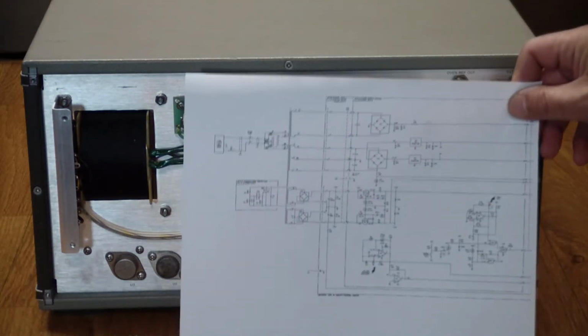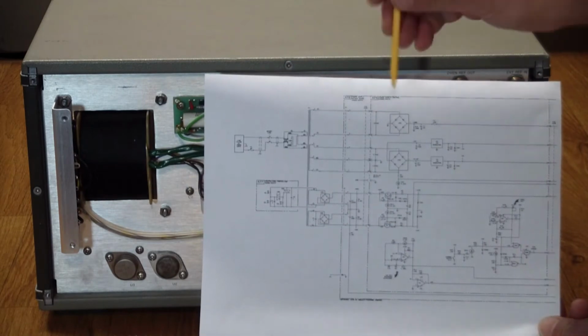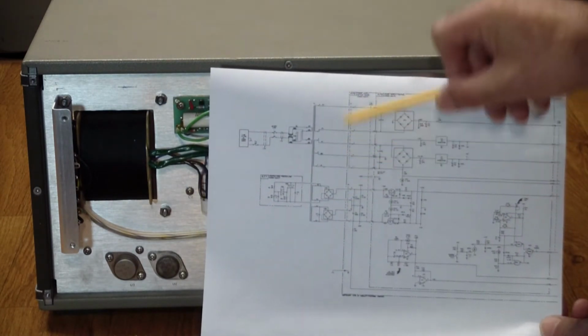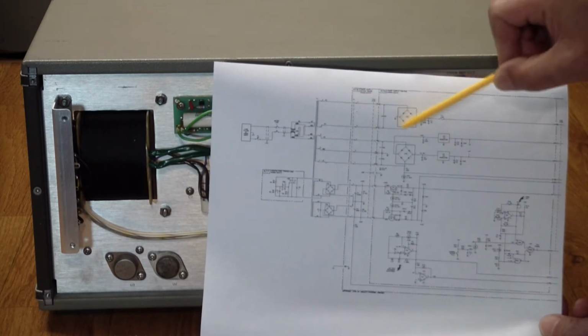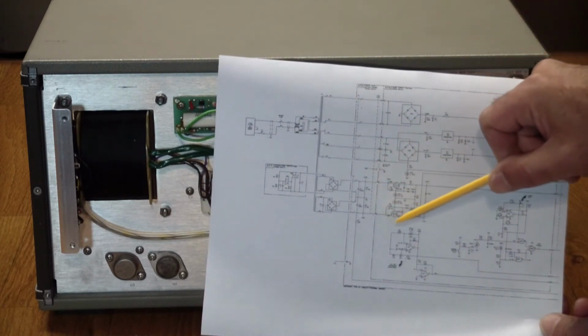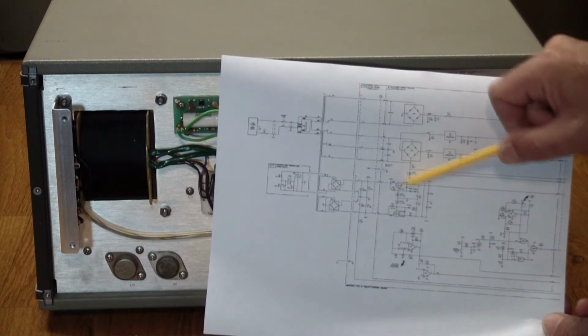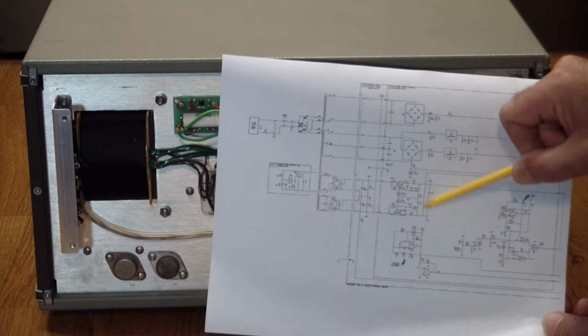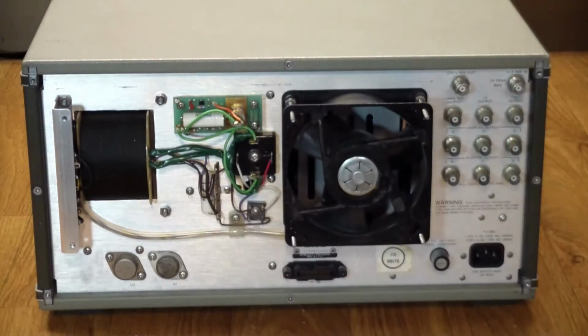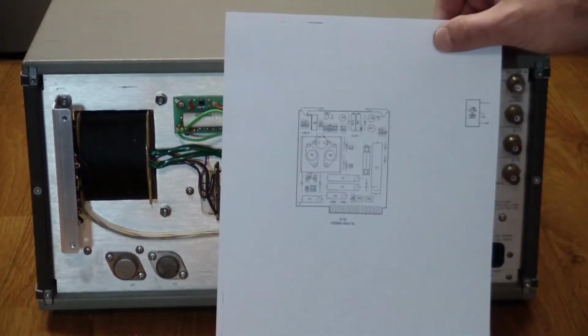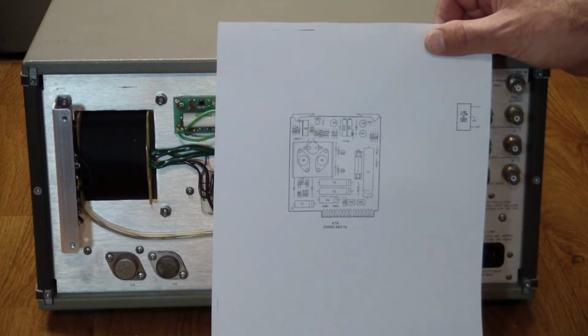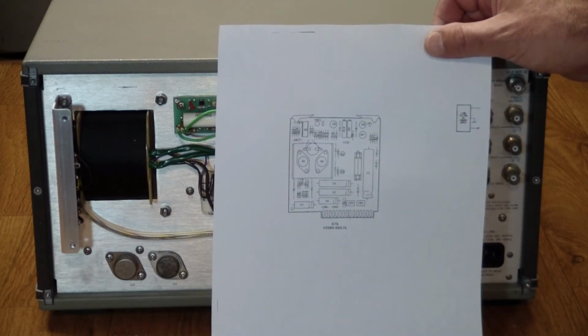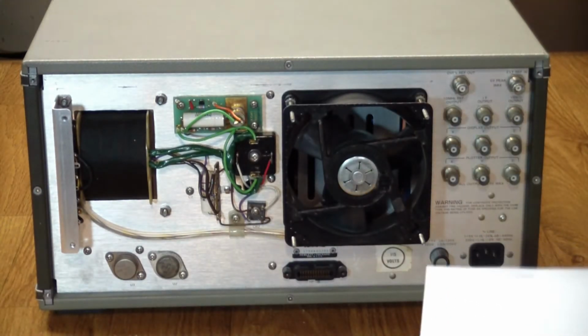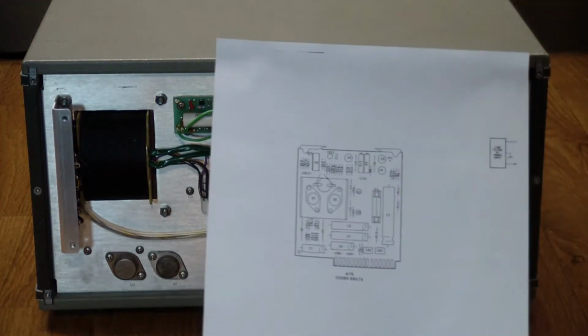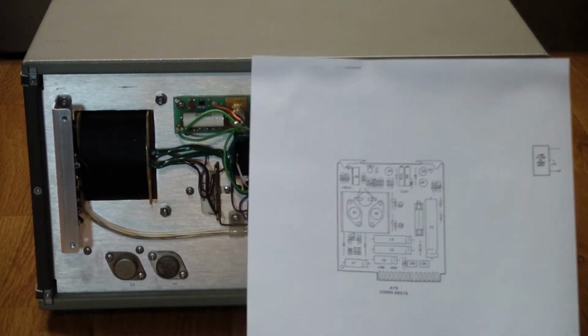Going back to the schematic here, we basically see that there are several secondary voltages being fed out. They're further rectified here, and we start to get some regulated voltages here. Plus minus 24 volts is generated here, and that is generated on a board inside that looks like this. What I'm going to do now is find where the output of these bridges go to, hopefully find this board, and continue our troubleshooting.